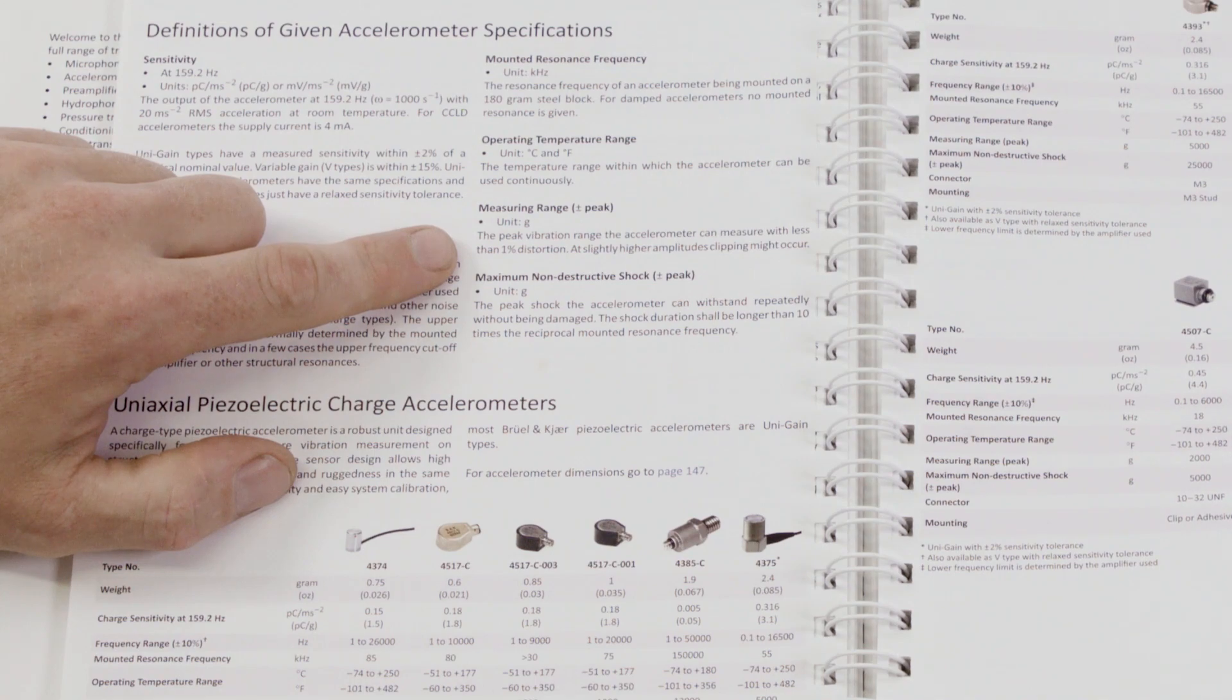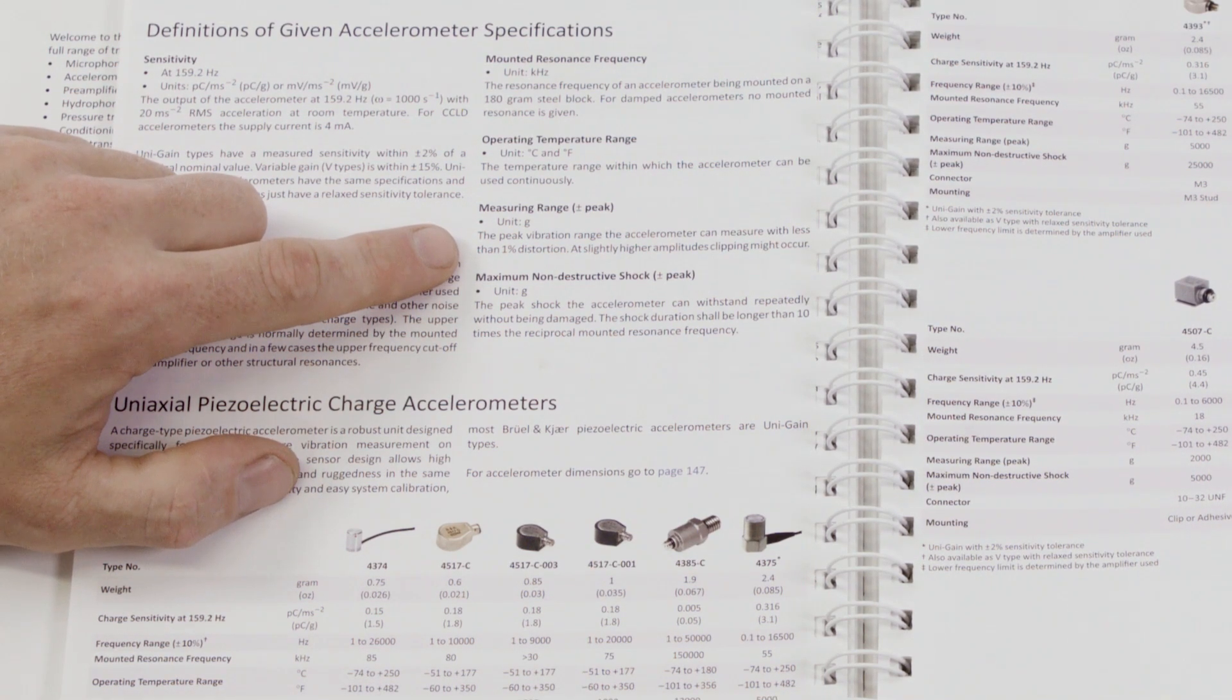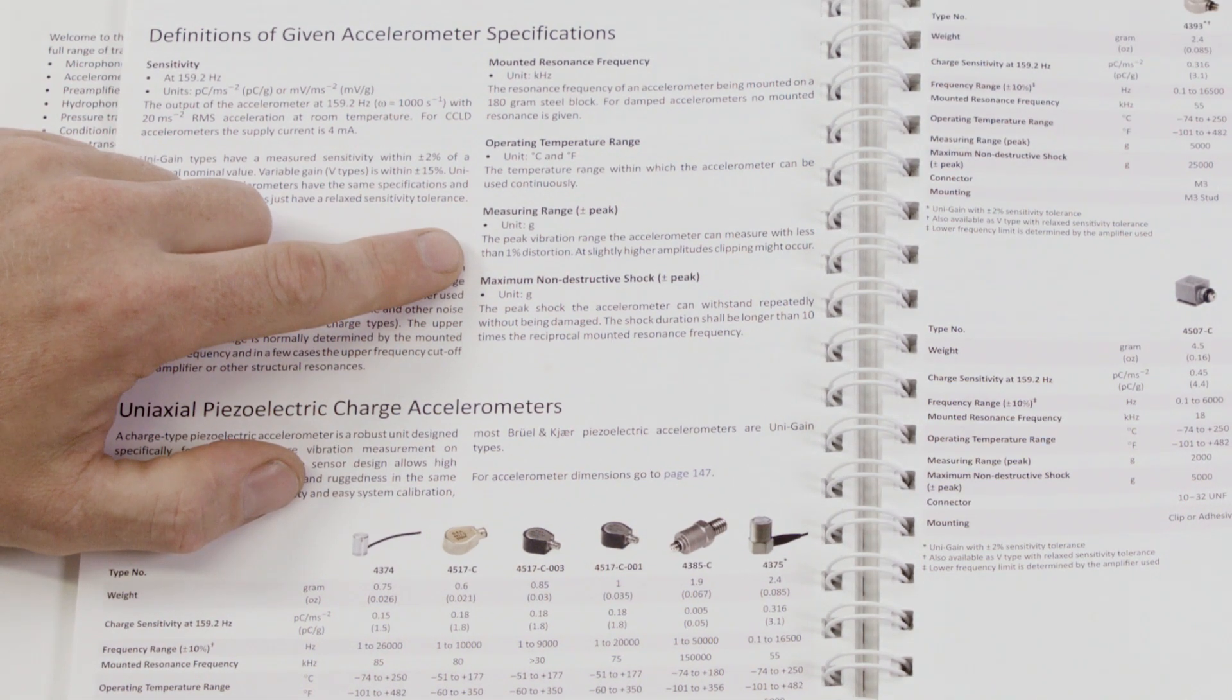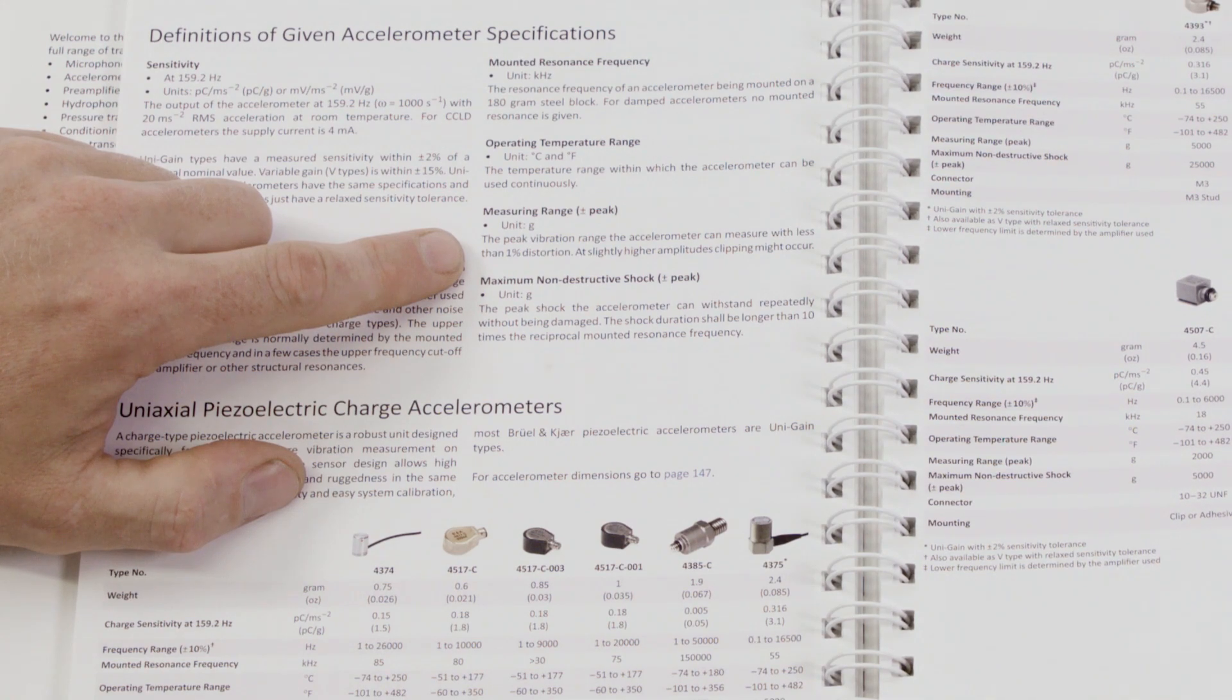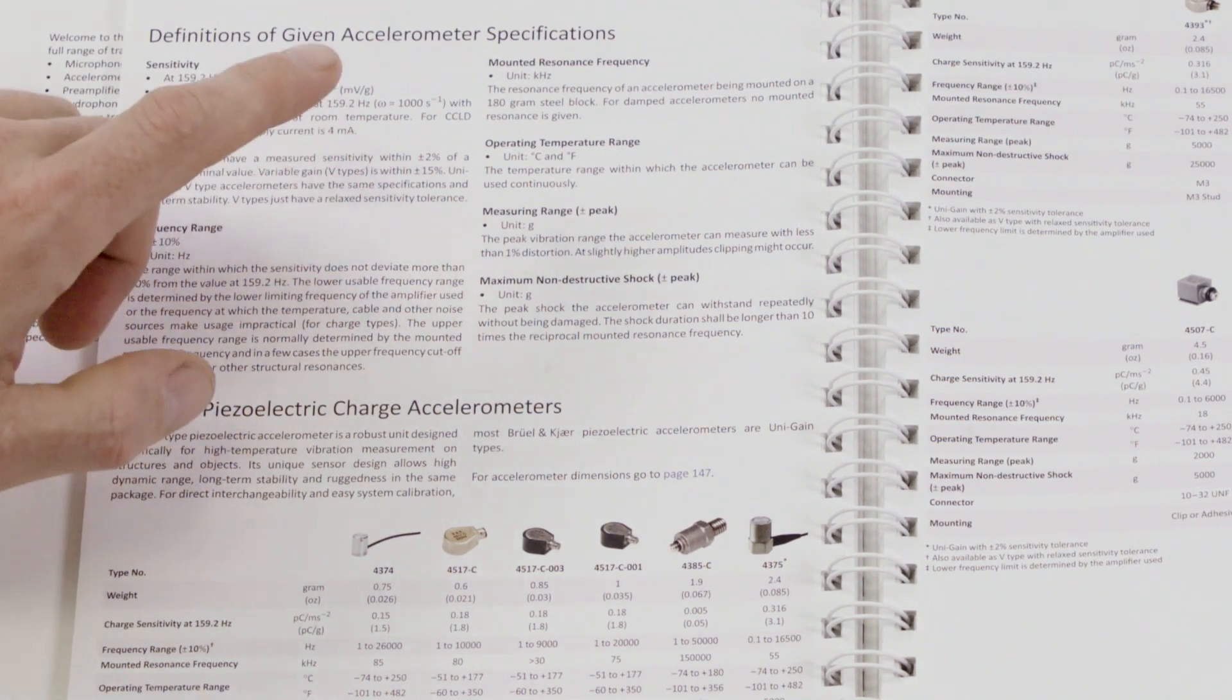It should be noted that upon impacting levels higher than the measuring range, overloads may incur that takes up to the start-up time, typically 10 or 30 seconds for CCLD accelerometers, before the accelerometer will recover to a measurable state.